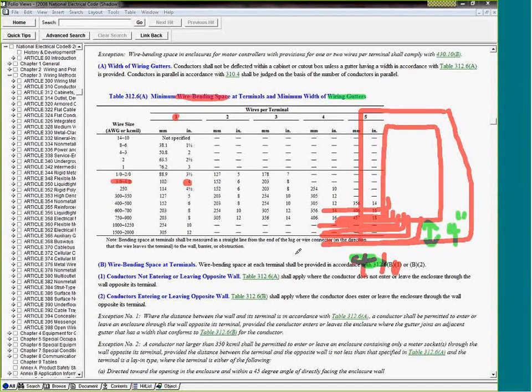So basically, 2 sets of conductors. Each one of them is 4 inches. Because of 2 sets, I'm paralleling. This is number 2, and because of that it will be 6 inches. My gutter, which is supposed to be 4 inches, now has to be 6 inches because of paralleling. The same applies if you parallel 3 sets, 4 sets, 5 sets, all the way.